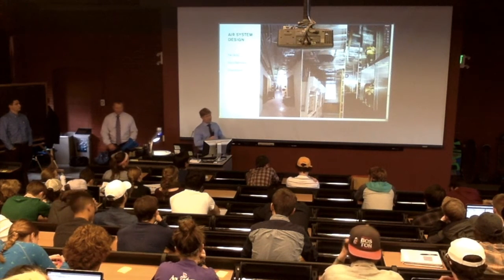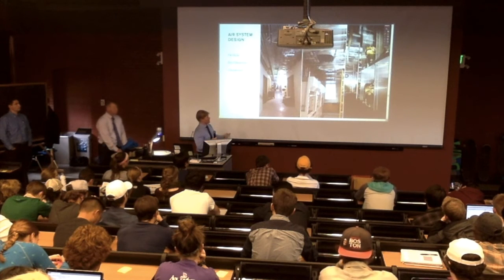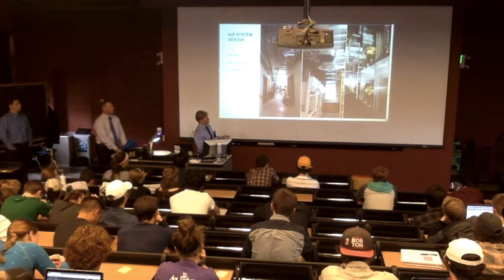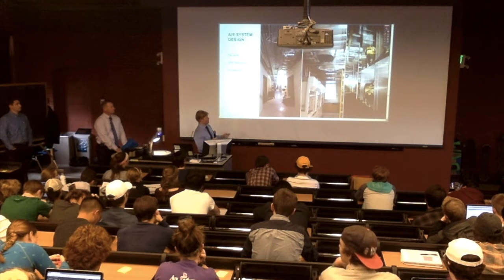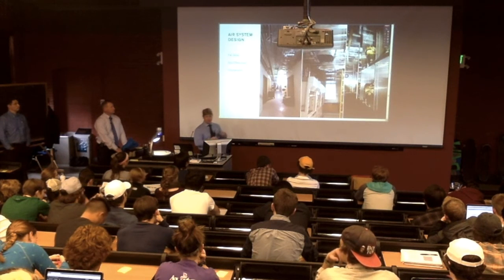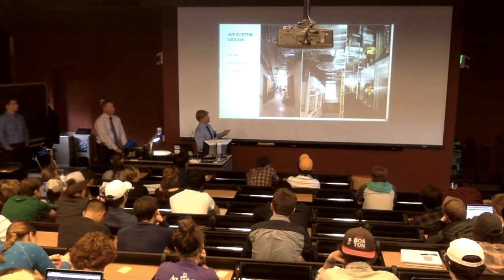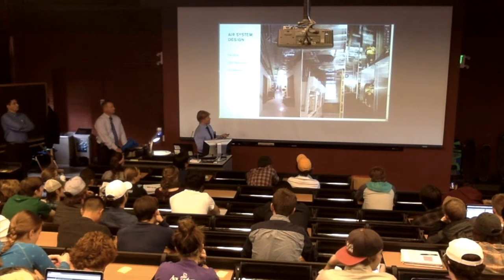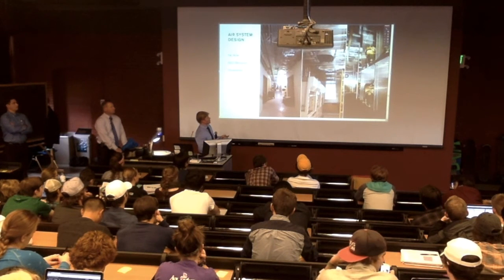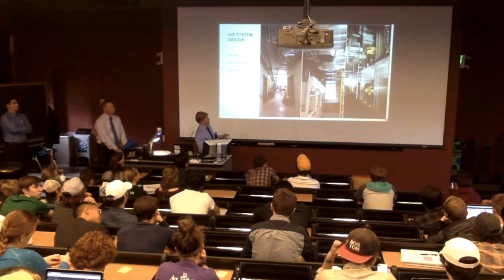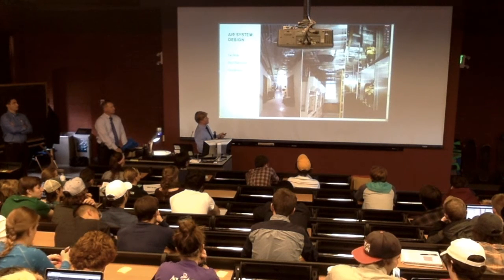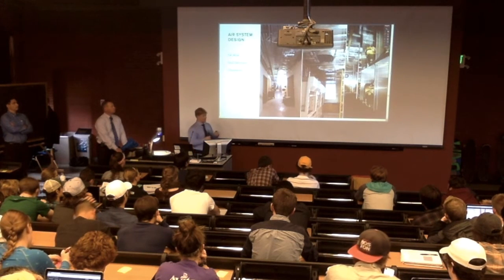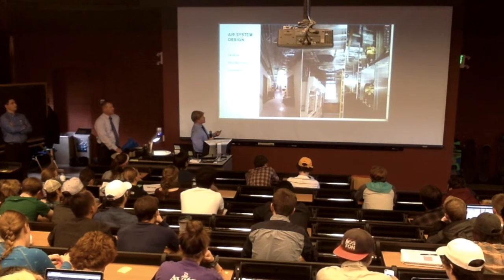If your air system goes down, your fume hoods cannot operate or become an unsafe condition if the fans go down. So that's why there are multiple stacks on that building, which are redundant fans, so the fume hoods always remain safe. So these pictures just illustrate all the ducts that go down and the pipes that cross up. And these are pictures from right across the street.